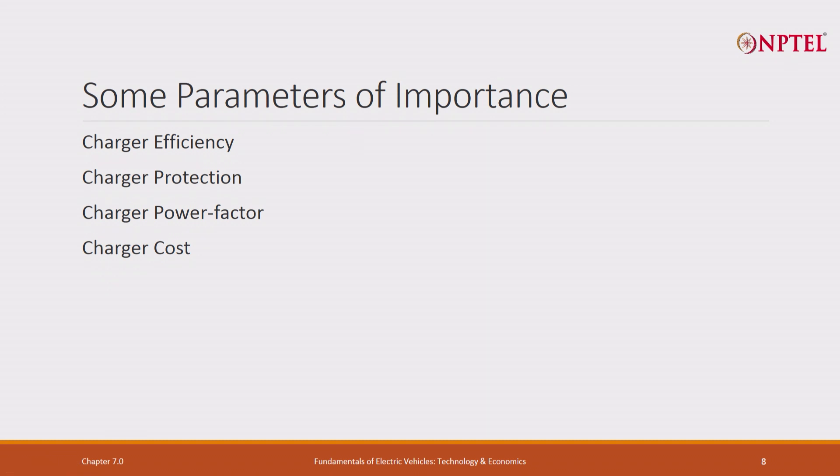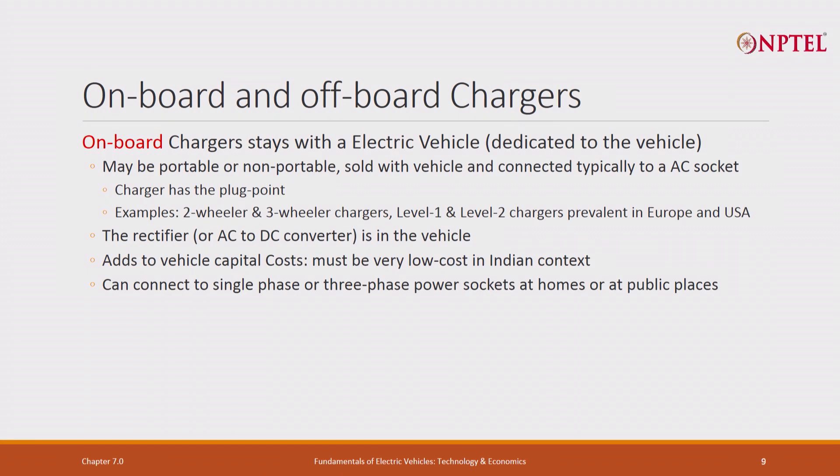Some of the parameters that are of importance. Charger efficiency. Why efficiency? Suppose it is 90 percent efficiency. 10 percent power is wasted during charging. I am paying for it. One, I am wasting power. I am paying for it. It also produces heat. Good chargers should have a higher efficiency. Ideally 96, 97, 98 percent. Poor chargers will have 80 percent efficiency. There will be in between chargers. It depends on the cost. If you are willing to pay higher cost, you will get a higher charger efficiency. Charger protection should always be there. Charger power factor correction and charger cost. These are the four parameters that I have to worry about.